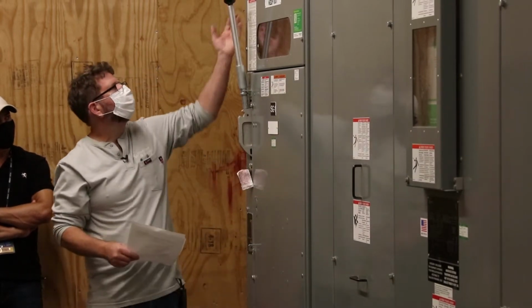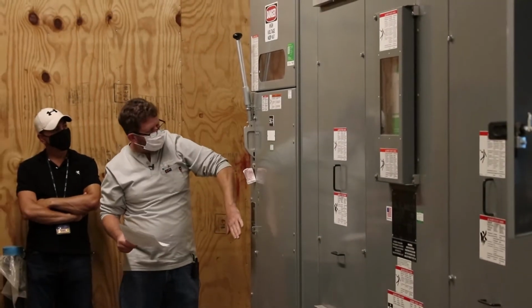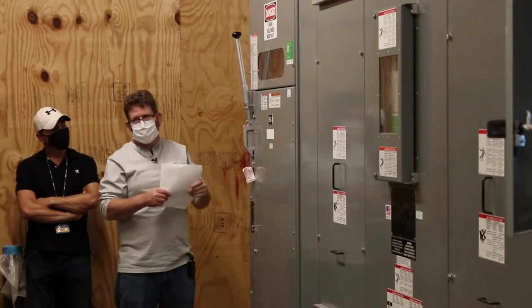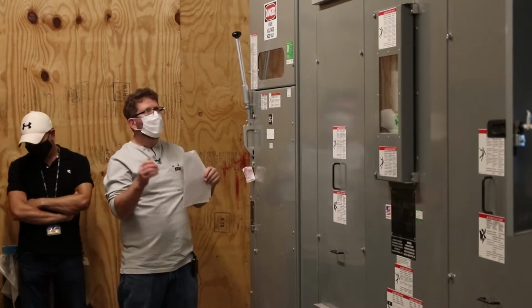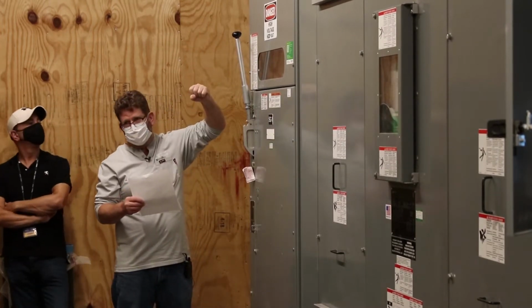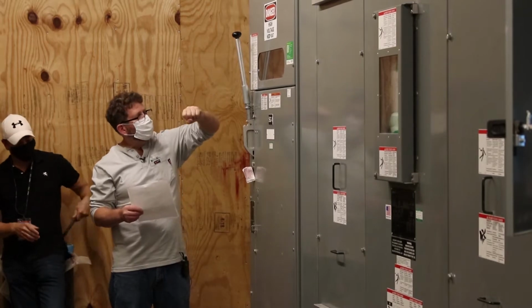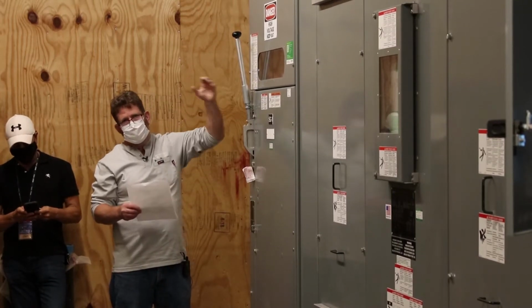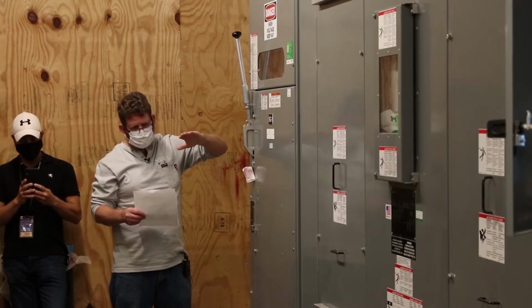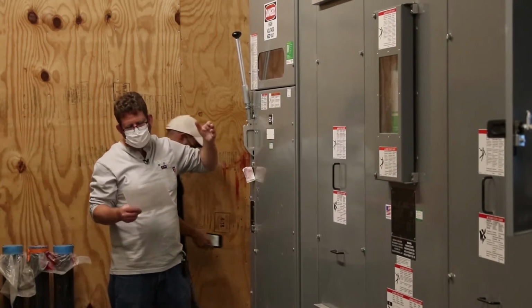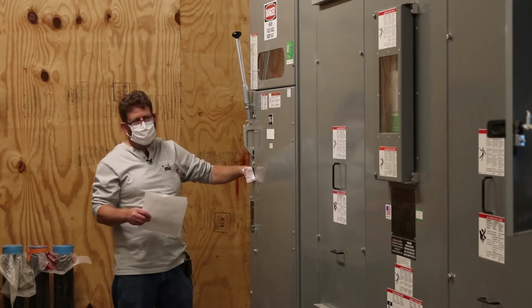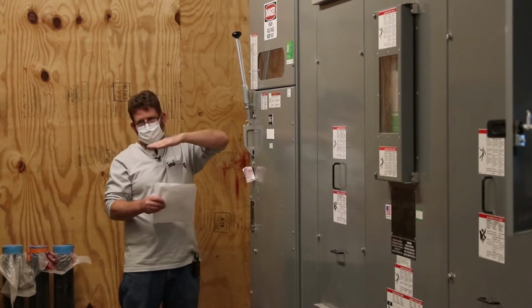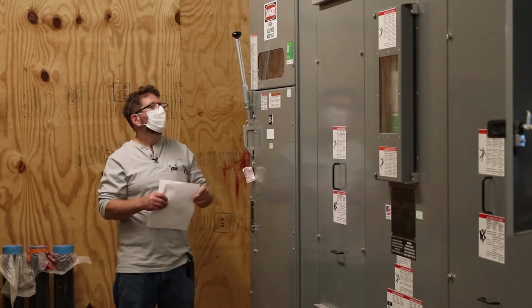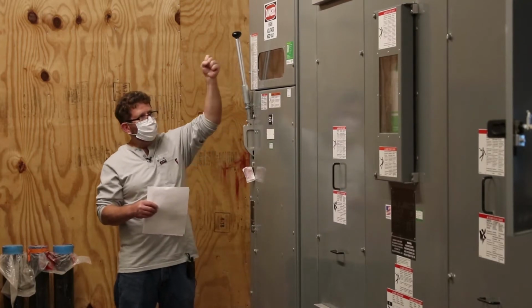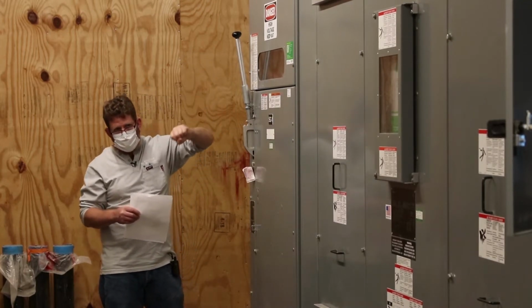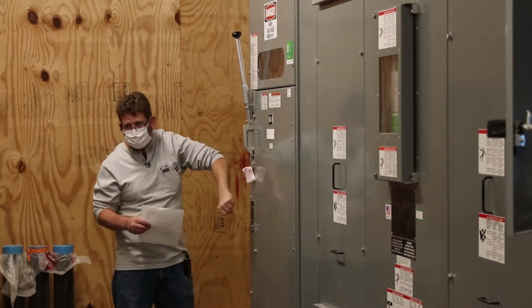When you open the switch, you pull the handle down right through the normal travel. The way this mechanism works, it's an over toggle mechanism. As you're pulling this down, you're compressing a spring. Once you go over top dead center, the spring's going to unlatch. It's not really a latch, but it's going to go over toggle and release, slamming the blades open in a quick move. So you don't want to pull gently until over toggle and bring it down. You just want to bring it down in one quick motion.